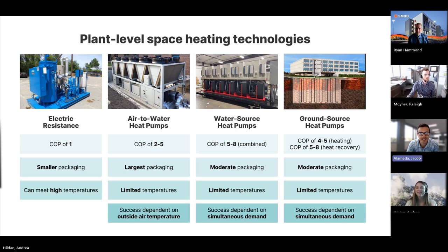But lastly, and I know I've talked a lot on this slide already, are the ground source heat pumps. These are pretty much water source heat pumps with a hydronic loop on each side of the heat pump. But this time the heat for your water source actually comes from the earth. This obviously isn't always an option, especially on retrofit projects where there isn't enough land available. But when it is a possibility, it's very efficient. You can exchange heat with the earth in either vertical or horizontal loops. The vertical bores go down hundreds of feet, between 150 and 400 feet down. The horizontal loops are typically only about 15 feet deep, but take up a lot more square footage. Using the heat from the earth gives you a very steady temperature year-round to either pull heat from to generate your heating hot water, or to put heat into when generating chilled water. So that is another option as well.